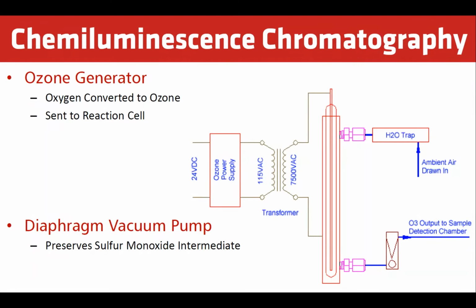Basically, what we do is we have our air drawn through the enclosed tube with electrodes down the center. We apply 7,500 volts to that electrode, and the electrode then produces ozone. The diaphragm vacuum pump preserves the sulfur monoxide intermediate. So once we get to the photomultiplier tube where the chemiluminescence happens, this all happens at a vacuum.